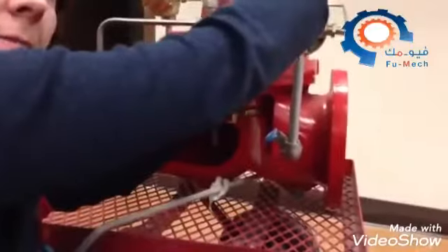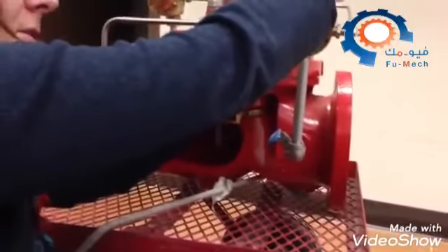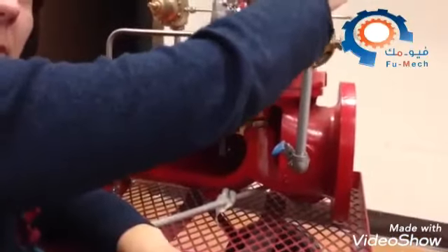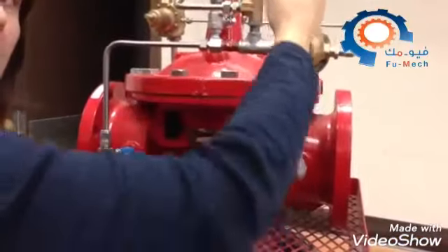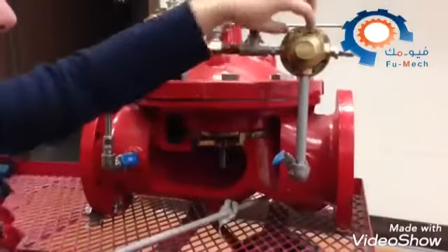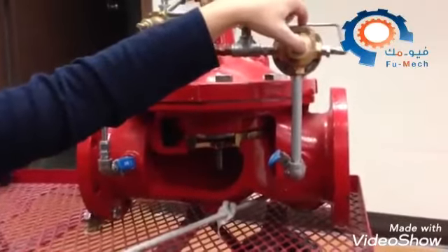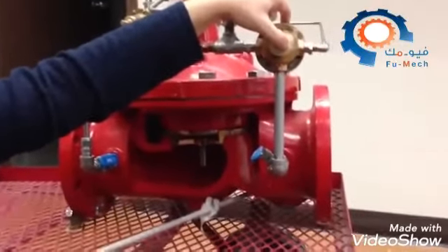on top of the bonnet, in the valve chamber on the top. So when that happens, the only force that's acting on this is the stem, the spring force, which is going to force the stem in this direction, which will then move the saddle assembly away from the seat, opening this valve. So this valve is going to fail open.